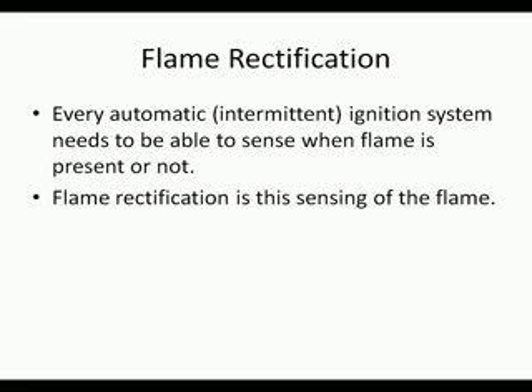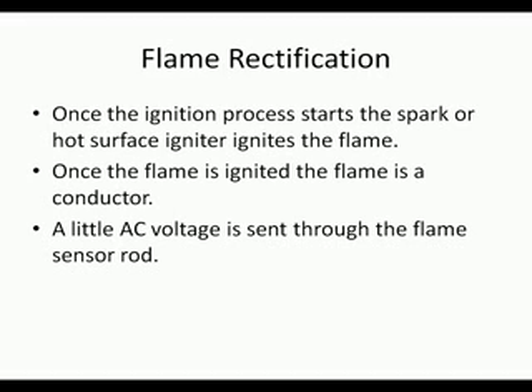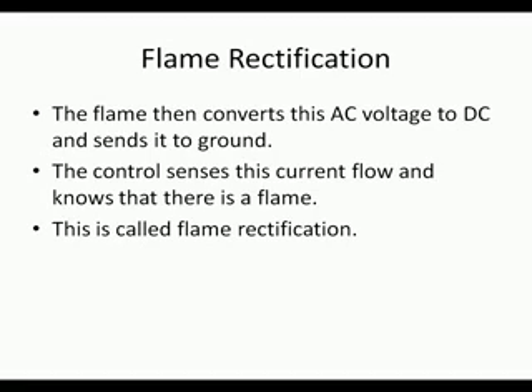With gas heat, we've continually talked about flame rectification. Flame rectification is the sensing of a flame. Every automatic ignition system needs to be able to sense when the flame is present or not. Without flame rectification, we might be dumping unburnt gas into the furnace room, and if there's any spark, this gas would ignite and cause an explosion.